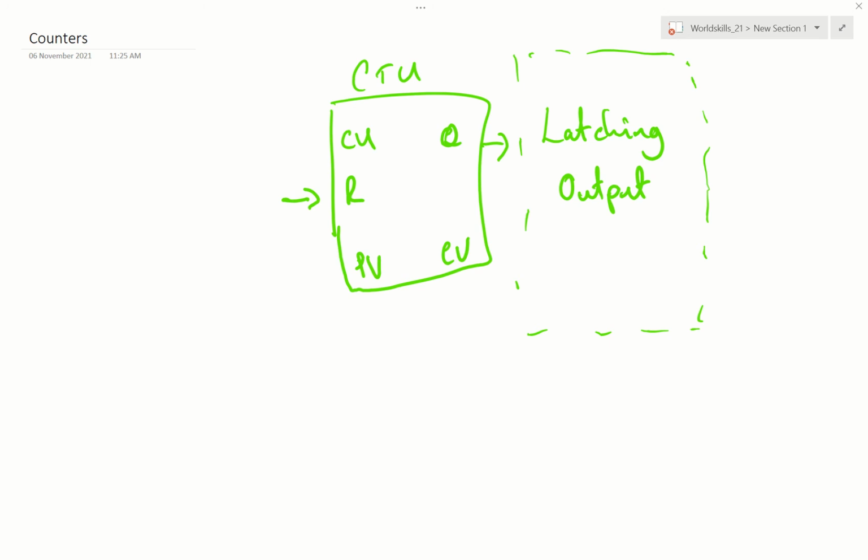But mostly when we're using the sequential integer method and we're looking to move through steps, this can be dangerous if we leave a move command in here. If we leave a move block connected here and we say, once we reach the count, move to step 50, that will cause us issues. That's not what we want to do. But when you're thinking about this and writing it out, it does make sense, and it's a trap that most people fall into, because we essentially want to say, keep counting something, and when we count it, move to the next step.